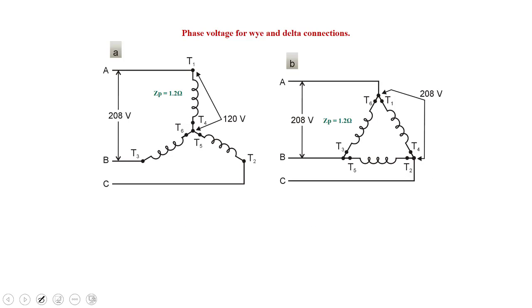So if we look at a six lead motor, we see that there's coil 1, 4, 2, 5, and 3, 6. And if we make the star with 4, 5, and 6, we now have those motor windings connected up in Y. Versus the diagram over here, we can go 4 goes to 2, 5 goes to 3, and 6 goes to 1, and then we supply 3-phase power. So we can also connect them up in delta.